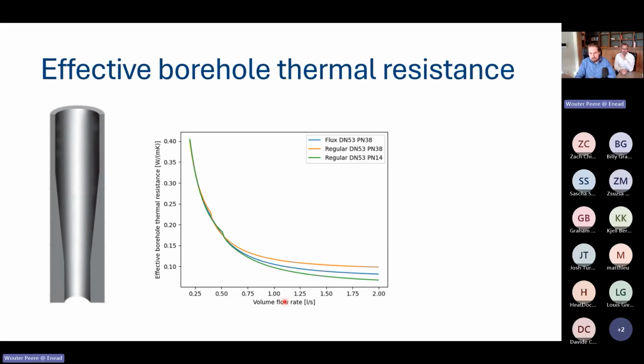So once we are in this range, it's actually the average wall thickness that plays an important role. And since the flux has a conical design and hence on average a smaller wall thickness, the heat transfer in this turbulent regime is actually better than the regular probe. So also from a thermal point of view, for higher flow rates, for higher Reynolds numbers, the thermal performance is better than with the traditional regular smooth pipe with the same pressure resistance. So now I hand it back to Sasha to introduce two cases, and then we will take a look at how these theoretical graphs now relate to real-life projects.